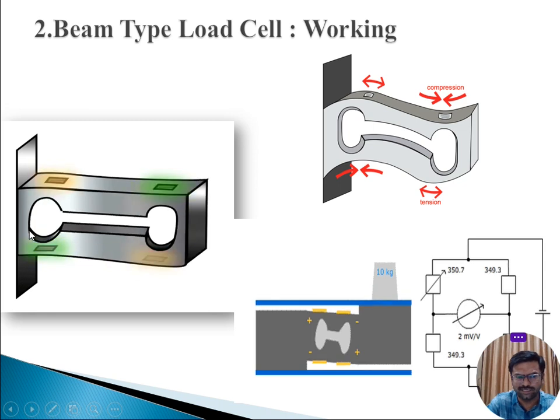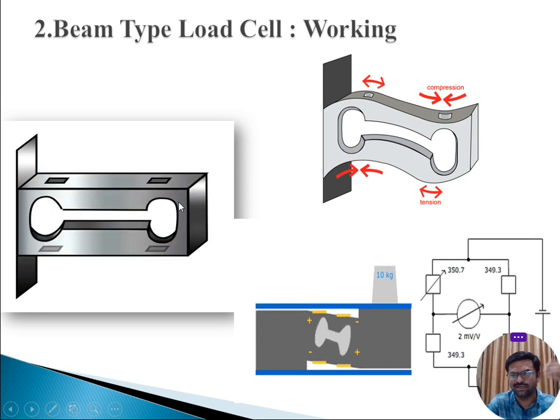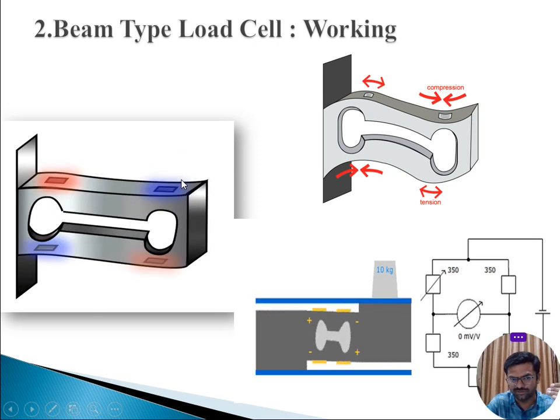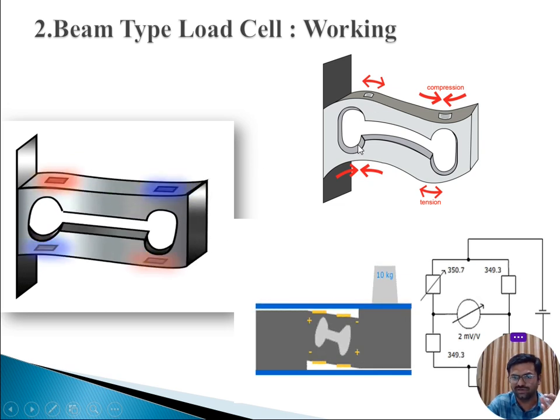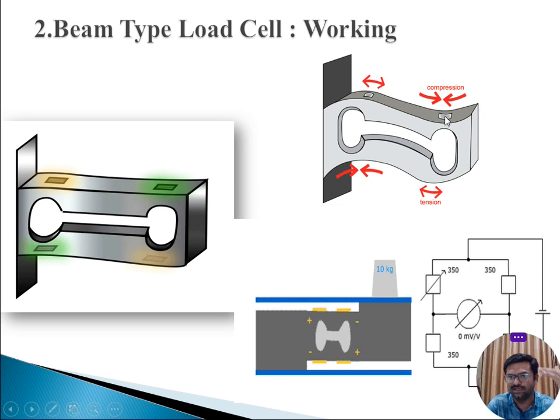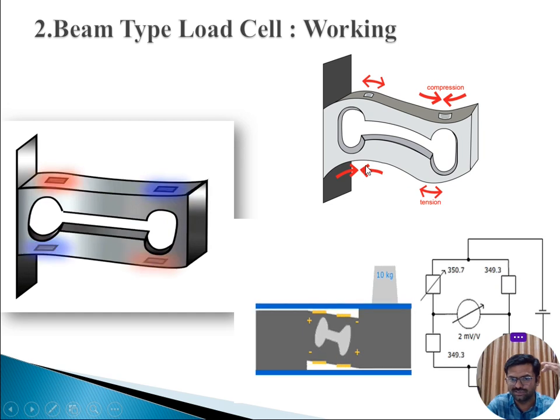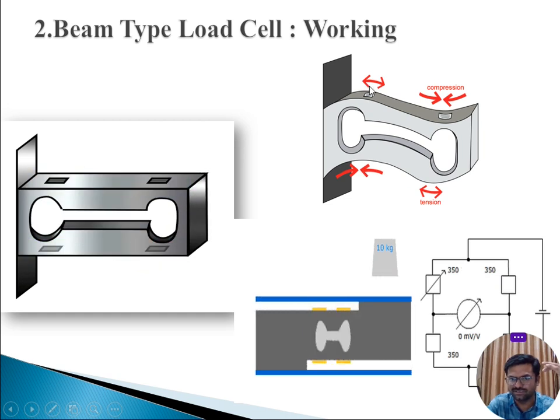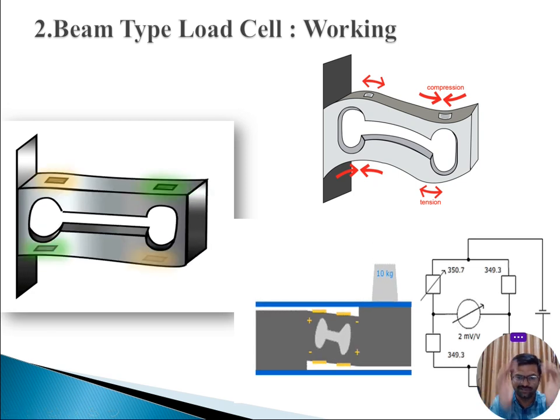For the beam type load cell, one end is connected to a rigid support and the other end is hanging with a spring. When you apply a certain force, the beam moves. You can observe there are four strain gauges. When force is applied, the first strain gauge experiences compression, the second experiences tension, the third experiences compression, and the fourth experiences tension.